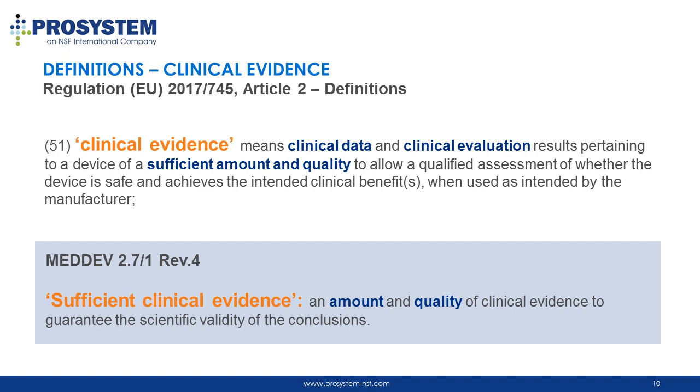The regulation also defines the term clinical evidence, which means clinical data and clinical evaluation results pertaining to a device of a sufficient amount and quality to allow a qualified assessment of whether the device is safe and achieves the intended clinical benefits. This definition brings us to another question. What is sufficient clinical evidence? To help clarify this term, we can consult the MEDDEV guideline. There, we read that amounts and quality of data are important criteria that should be taken into account to define sufficient.